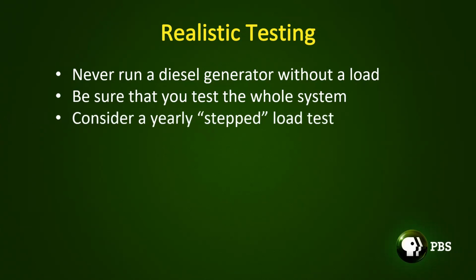This is something that you may or may not be able to talk the boss into. I consider it pretty essential, particularly for larger generators. That's a yearly stepped load test. And this basically is done by usually the diesel mechanics. They bring in a dummy load, which basically can take the full output of your generator, and they isolate the generator from the load and direct it to the load bank.